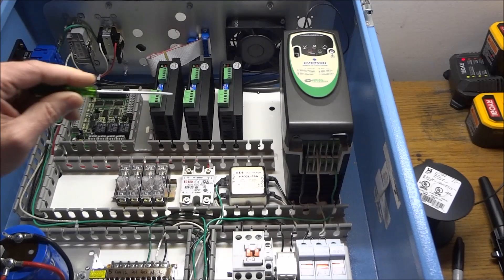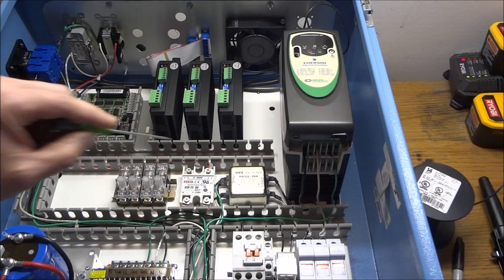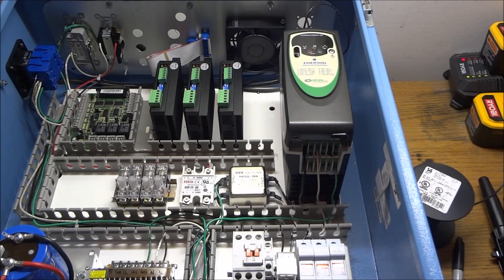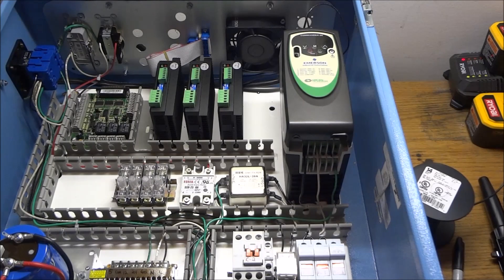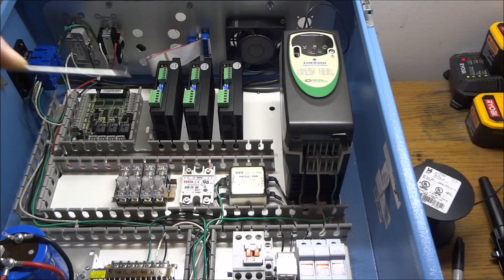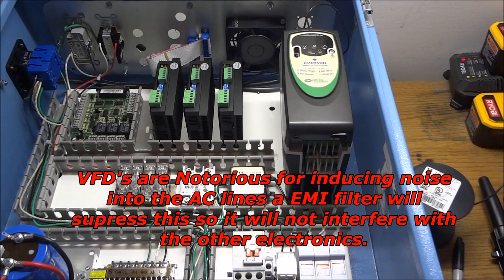I wanted to take a minute and talk about the VFD and the EMI filter. I've gotten several questions in my G0602 project as well as this project. And sometimes I just get random questions from individuals that are having issues with their system with noise or erratic behavior. If you have a VFD, you have to have a filter on the incoming power. If not, it's going to cause you issues.